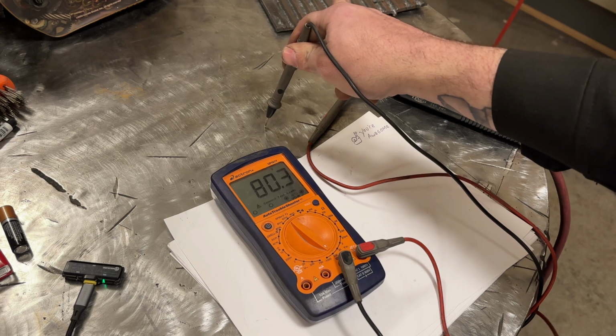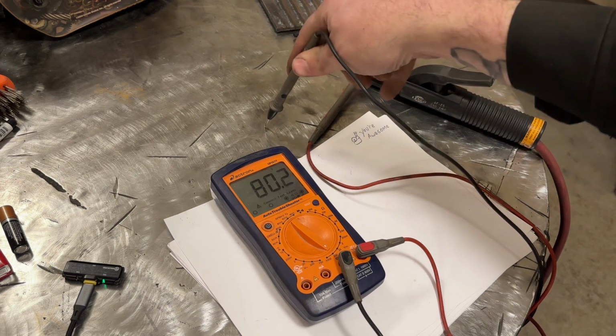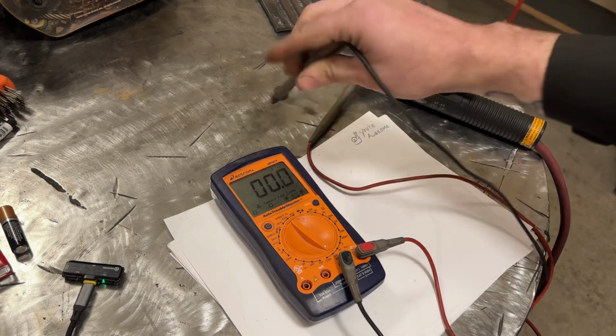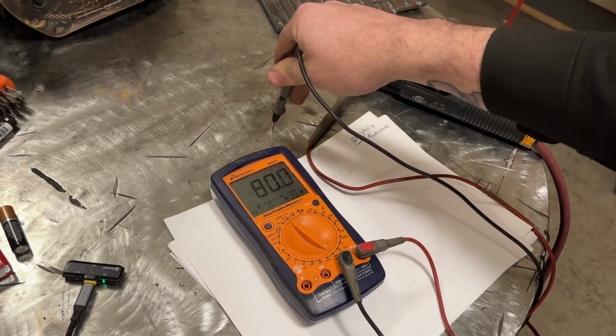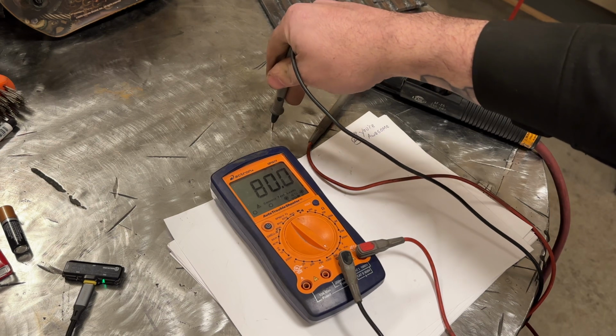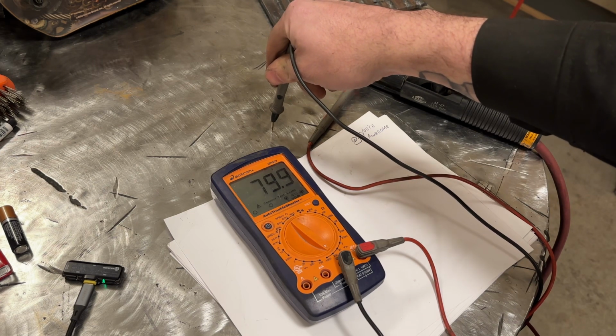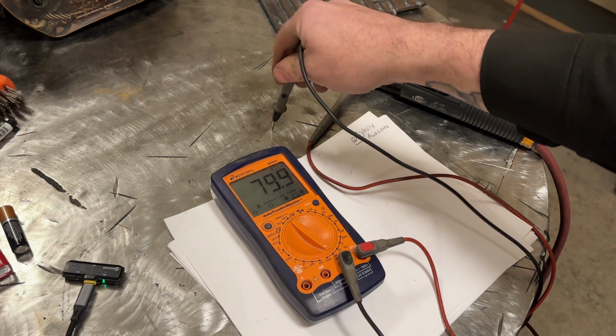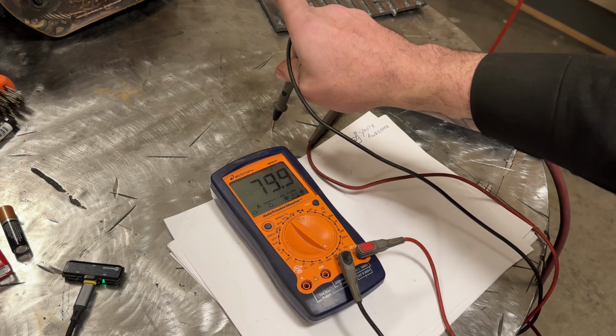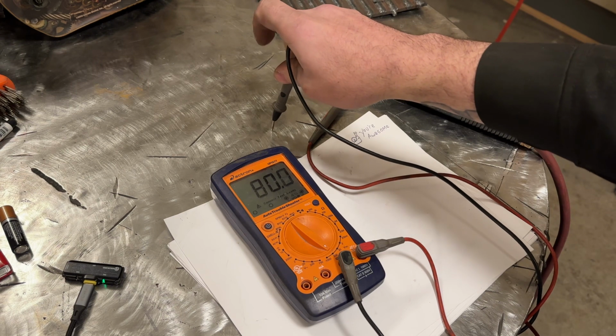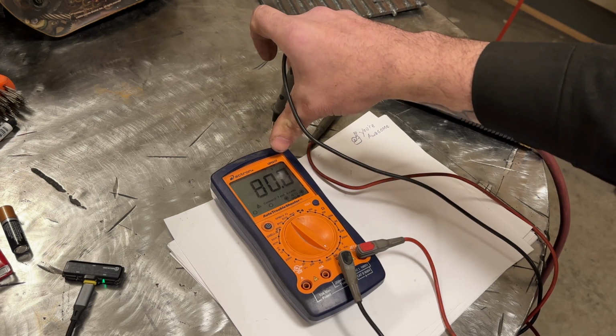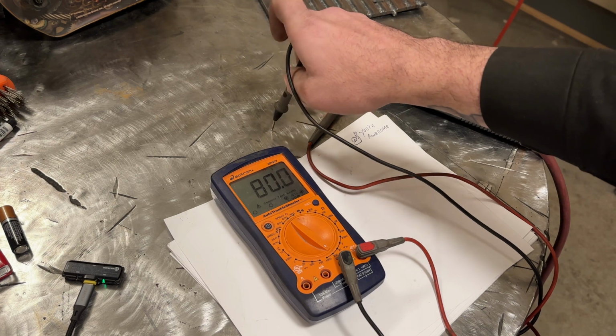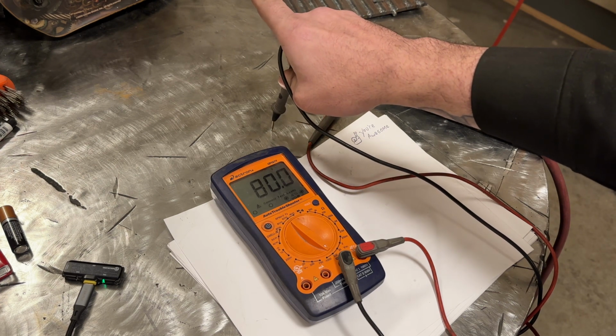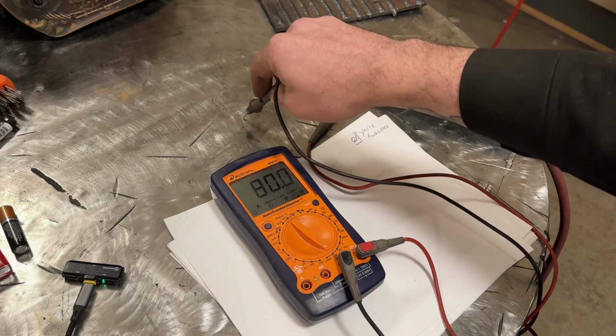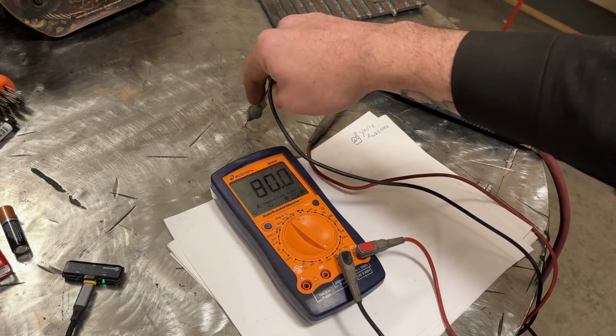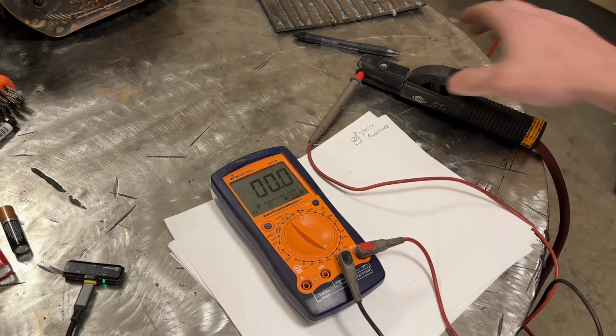So what I find interesting is we're going from essentially this stinger all the way through the meter into the table, and then it's returning back to the ground on the machine. What I find interesting is that this is reading exactly what the machine is reading over there—it says 79.9 on the welder, so the open circuit voltage reads exactly the same as the machine. But when we checked it directly, it wasn't reading the same, so I must not have had a good enough contact, but we were exactly at 80 volts. So that's interesting.